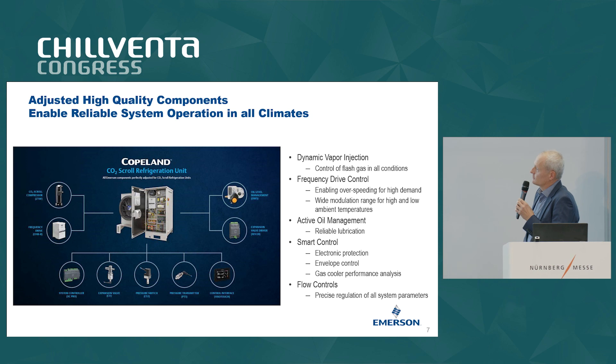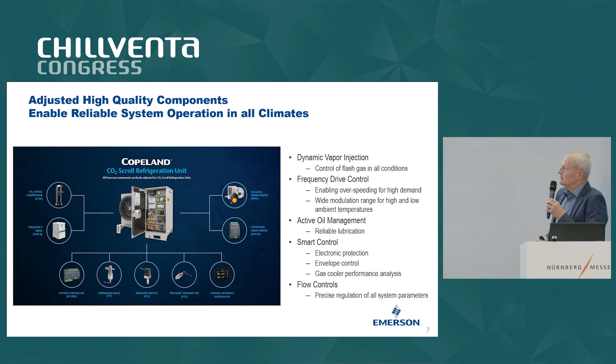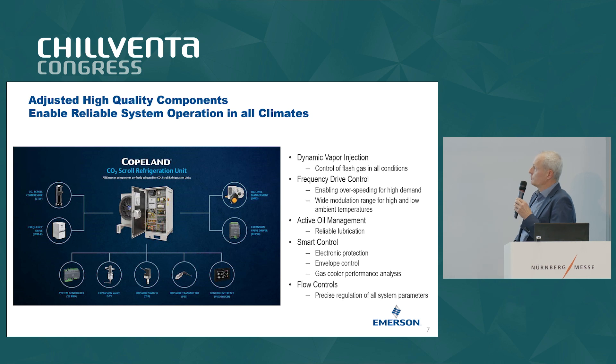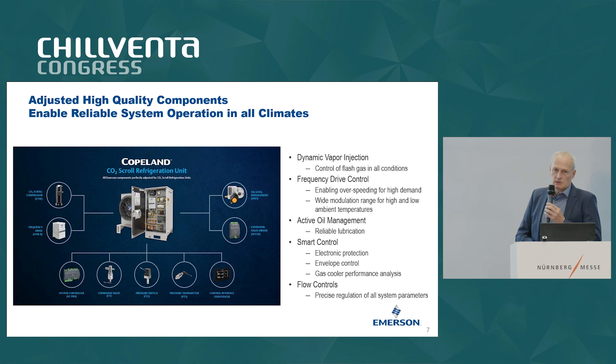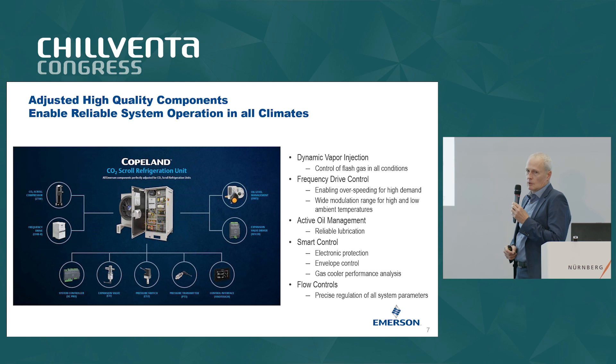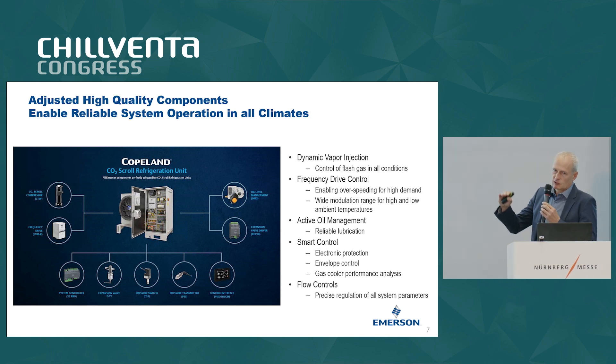Especially for CO2 it's important to have advanced and very tight control, and here we took the flow controls and control components out of our Emerson toolbox. Because we apply a new technology — CO2 transcritical scroll with dynamic vapor injection — we need a dedicated control especially to control the intermediate pressure and the level of vapor injected into the compressor. We also have stepless control via a variable frequency drive from our own portfolio. Very important, especially because we can split the system, is active oil management: the units are equipped with an oil separator and the OM5 oil management system to guarantee a sufficient level of oil at the compressor.